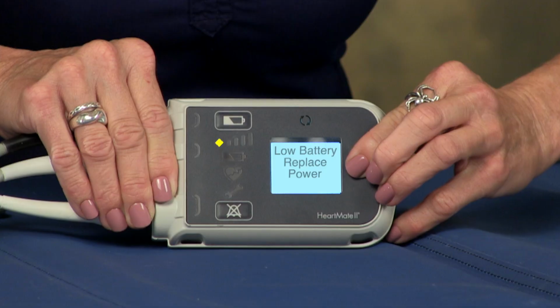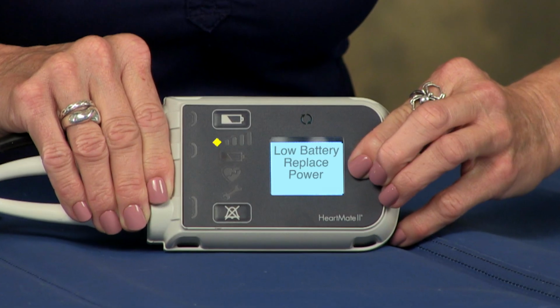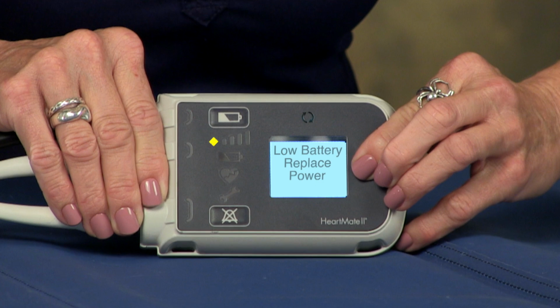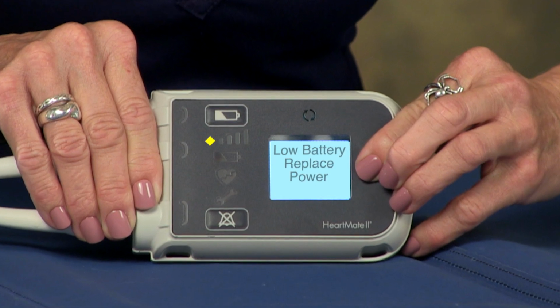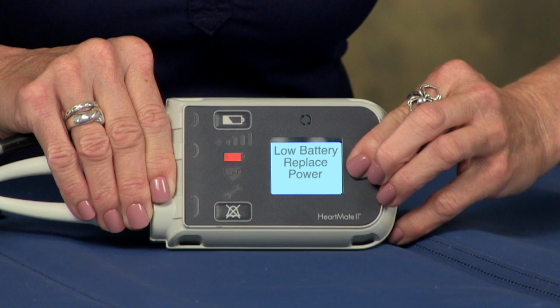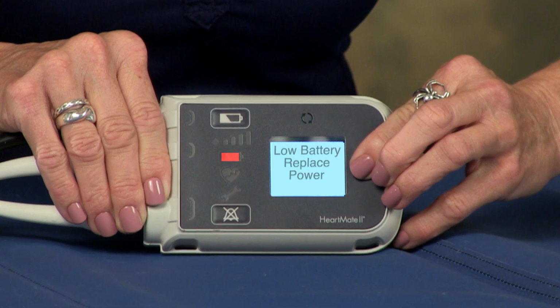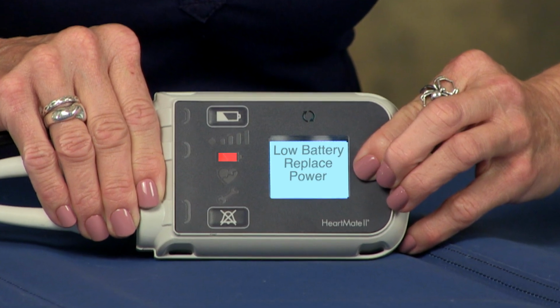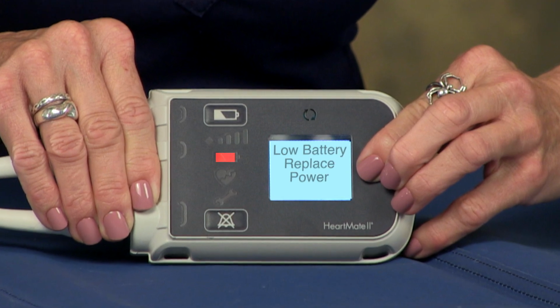If while you are transporting the patient a yellow diamond alarm occurs with the message low battery, replace power, you can get a pair of batteries from their backup bag. Press the battery clip release button to remove the low batteries one at a time and snap in the new batteries. If you don't change the batteries when the yellow alarm occurs, an annoying red battery alarm will sound. It doesn't matter how much time you have, please change the batteries when it indicates to do so.